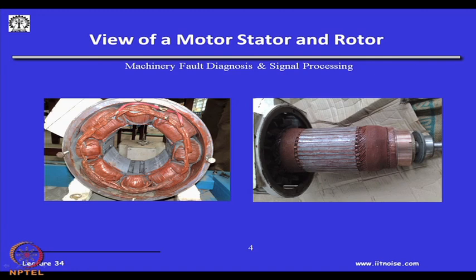Obviously, big motors require a lot of other functions, because of the eddy current losses, there will be a lot of heat generation. So, you would have seen that when a motor runs, it becomes hot. And if the heat is not dissipated, the temperature is going to rise. Once the temperature rises, it may have many effects. It may heat up the coils, it may degrade the insulation, it may damage the bearings, because the lubrication in the bearings will get baked. Once this lubrication gets baked, there will be hard particles, and they are going to scrape the inner surface and the bearings will become rough. So, one leads to another when you have a fault developing in an electrical motor.